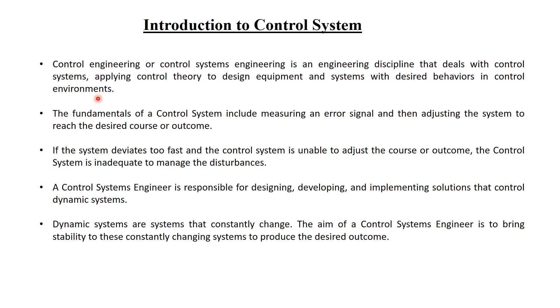If it is unable to, because suppose it is taking 1 hour and still the temperature is not reaching 20 degrees, that means the control system inside the air conditioner is not accurate or adequate or proper. So the designer has to make adjustments so that even when the door is opening or closing, keeping all these things in mind, the AC should operate smoothly and the temperature should be reached within 10 to 15 minutes.